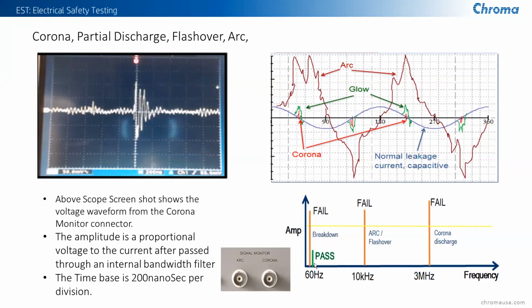Once you get above that, you'll see that it starts getting into what we refer to as a corona discharge. And our R&D group at Chroma have done a lot of evaluation. They've worked with various universities to be able to identify and characterize the differences between a corona and an actual arc and an actual breakdown when you're doing a high voltage test through the insulation.